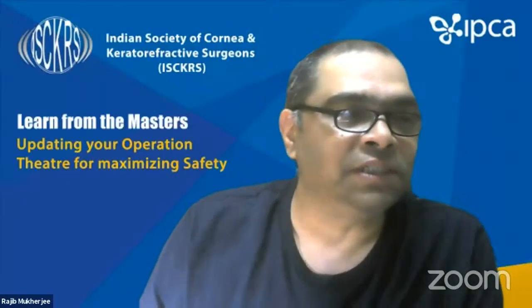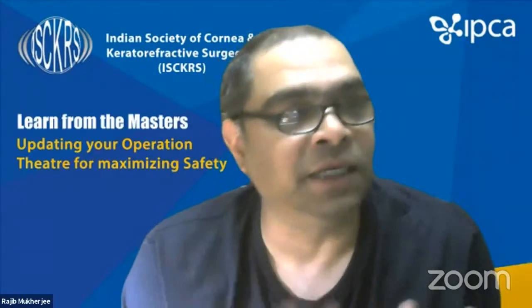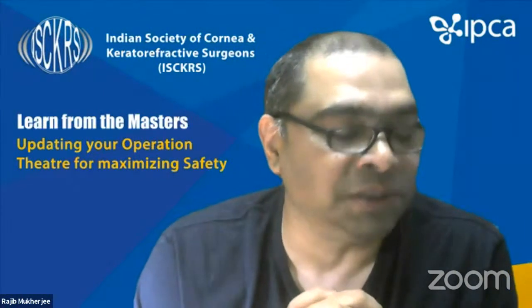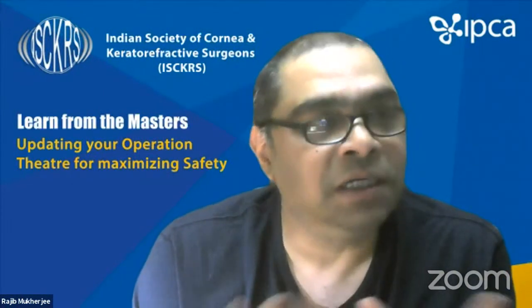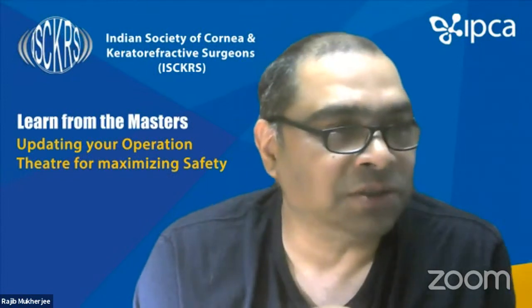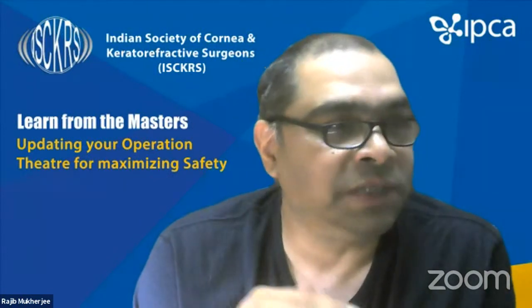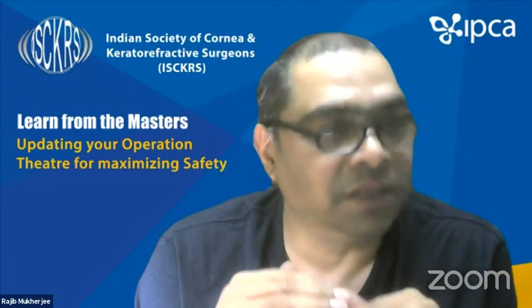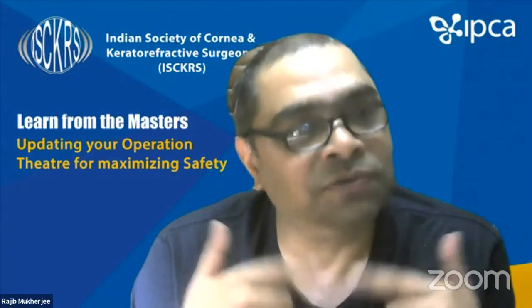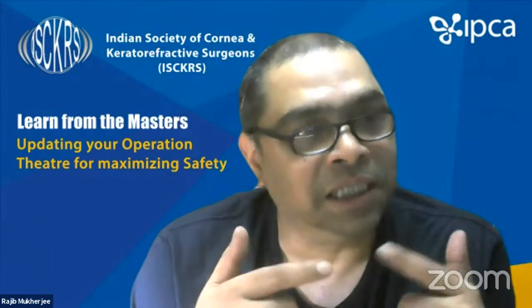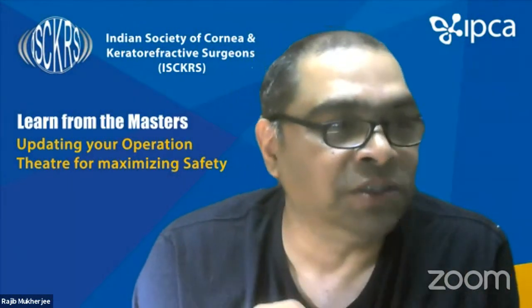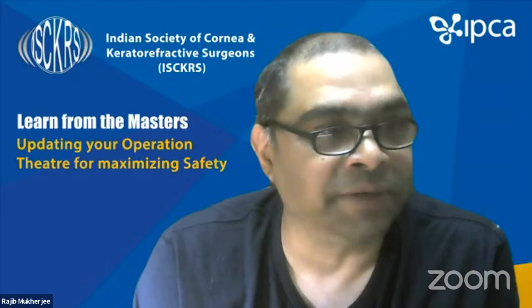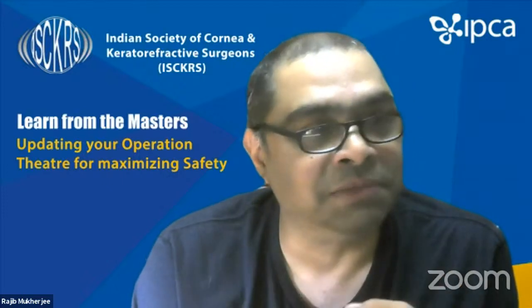One thing Dr. Ravindran saw in your video was about packing of your surgical instruments. In a particular video that you showed us, there were about 6 to 8 layers of cloth, right? Now, the number of layers of cotton cloth that keep increasing impedes the amount of steam that's going to flow eventually to the surgical instrument, which is deep inside. That is my concern, because it's a B-class autoclave. That's what we do when we validate the autoclave. The autoclave process should be stronger.